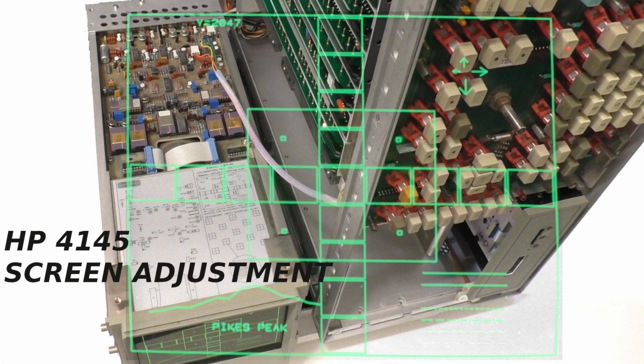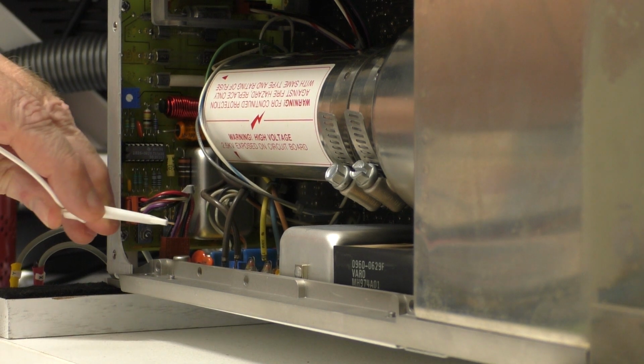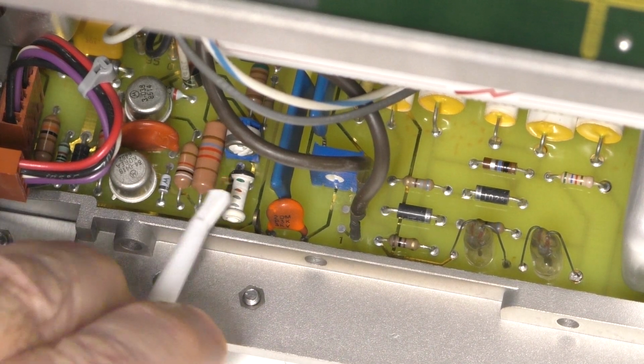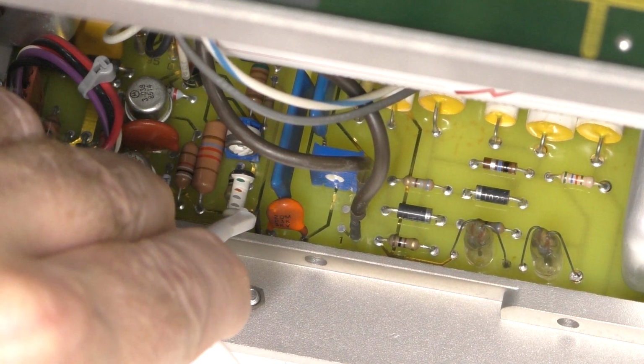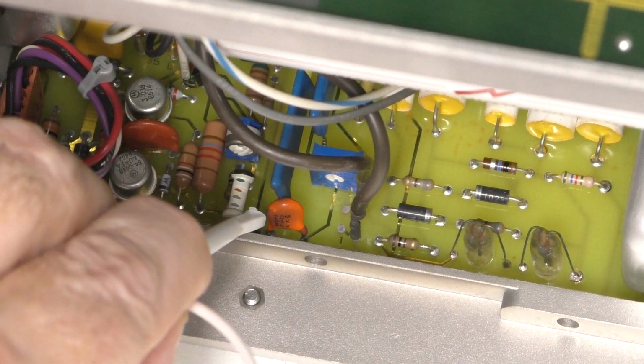Disconnect the probes from the A1 graphics display control board. Power down, and wait for supply to fully discharge. For this test we will attach a lead to the A4 high voltage board, put the display on its right side. Place a probe clip onto the A4 high voltage board, test point 1. The other end connect to the scope probe.